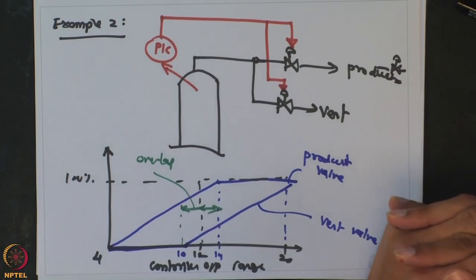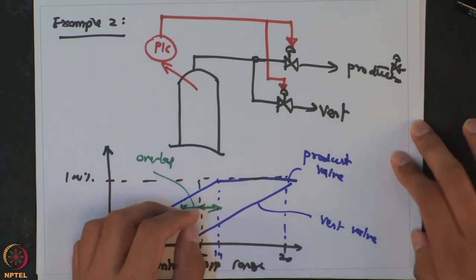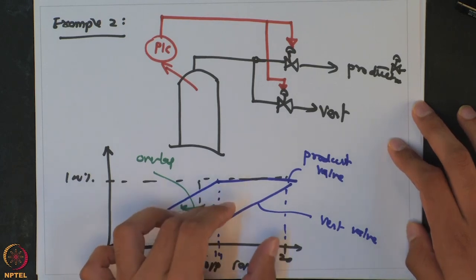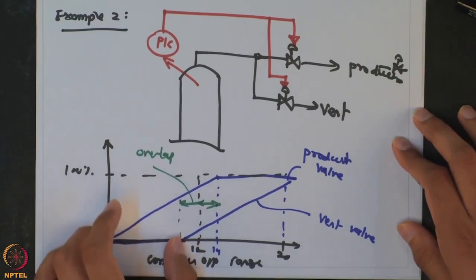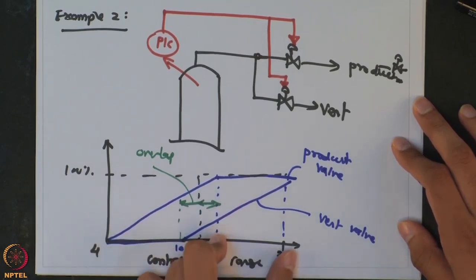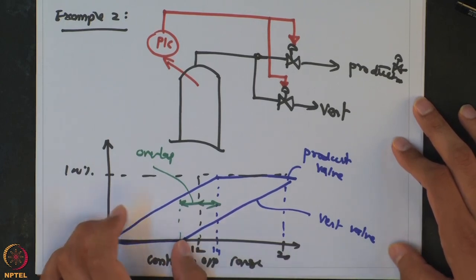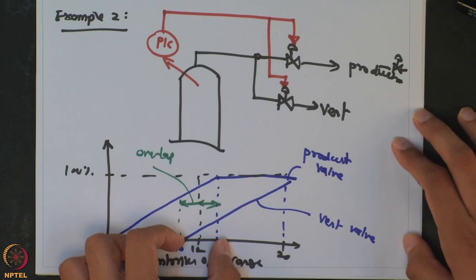Similarly, there are cases where you can have a dead band — a range over which no control action is taken. This is done when the two actions are mutually exclusive. A very commonly used example is a batch reactor where the same jacket is used for both heating and cooling. Up to a certain range you use hot fluid or steam to increase temperature, and in the later range you use cooling water — you do not want to mix steam with cooling water. So as a protection, there is a dead band where no control valve is operational. You can also have a dead band inside a split range design.